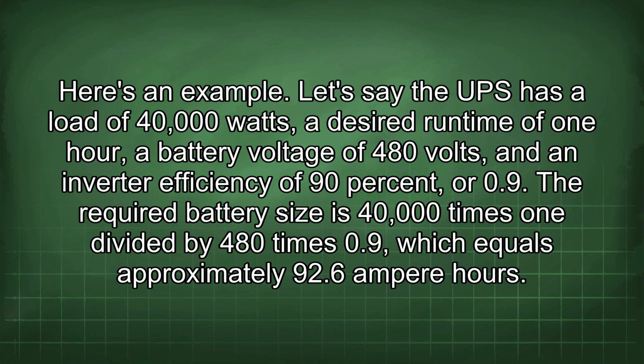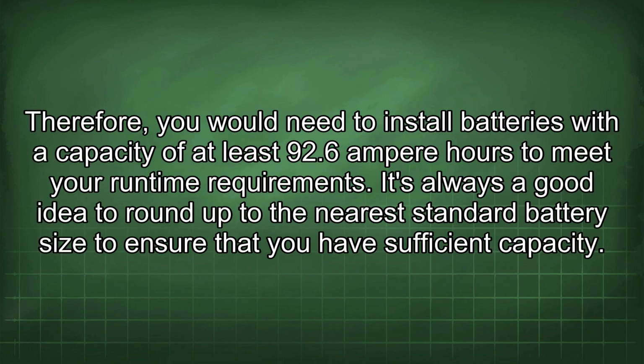Here's an example. Let's say the UPS has a load of 40,000 watts, a desired runtime of 1 hour, a battery voltage of 480 volts, and an inverter efficiency of 90%, or 0.9. The required battery size is 40,000 times 1 divided by 480 times 0.9, which equals approximately 92.6 ampere-hours. Therefore, you would need to install batteries with a capacity of at least 92.6 ampere-hours to meet your runtime requirements. It's always a good idea to round up to the nearest standard battery size to ensure that you have sufficient capacity.